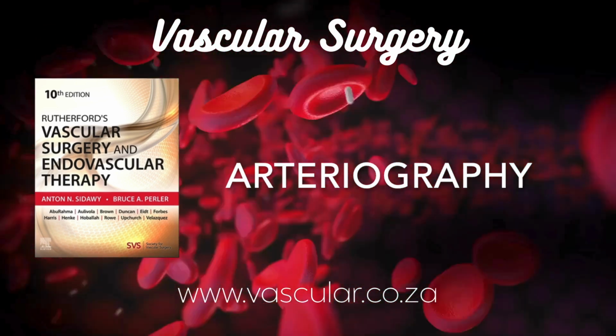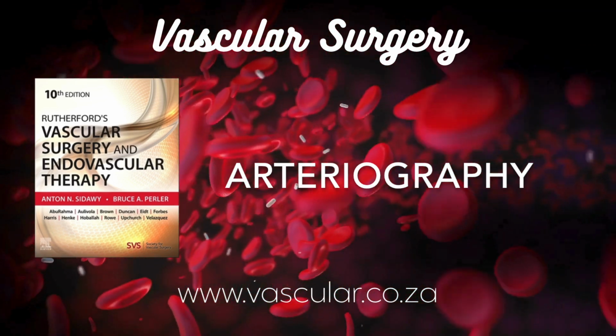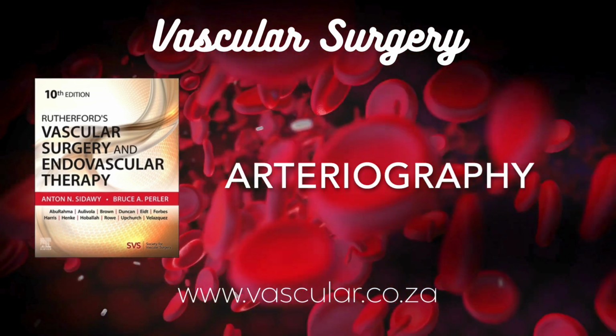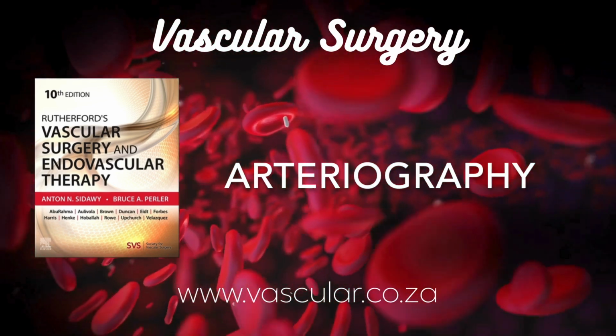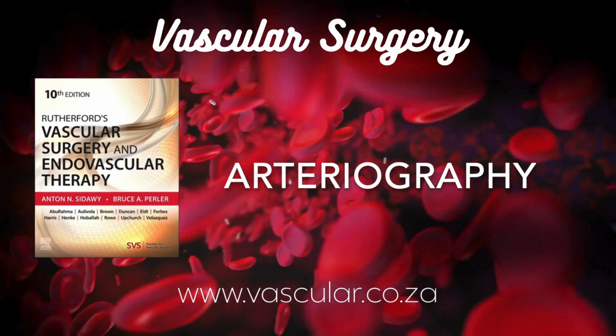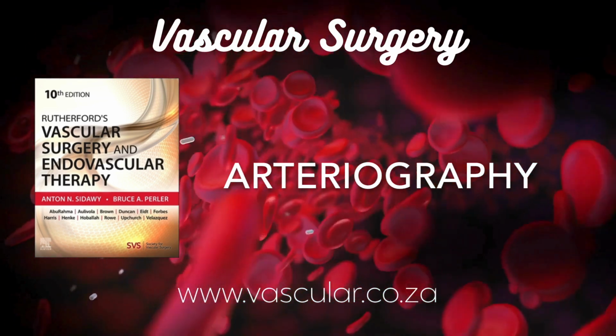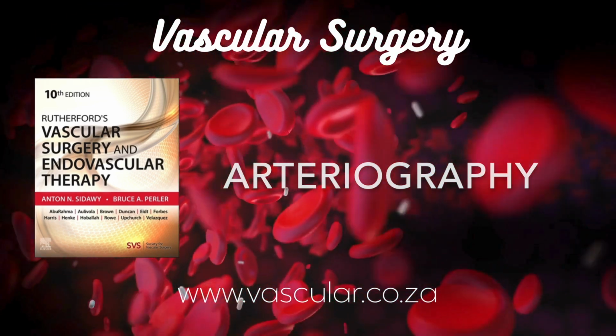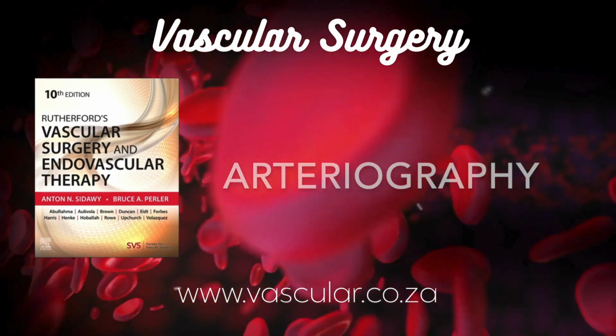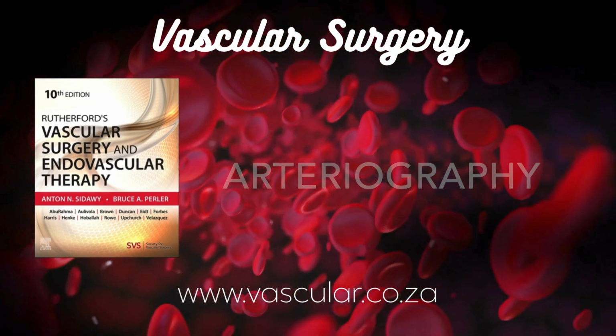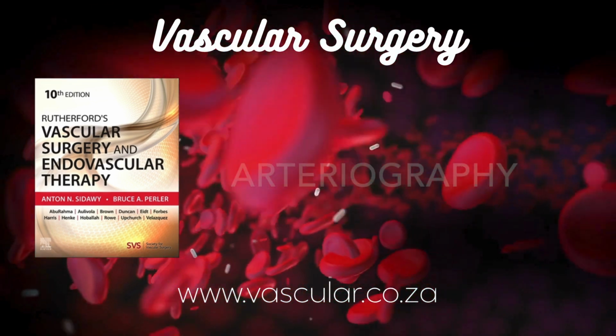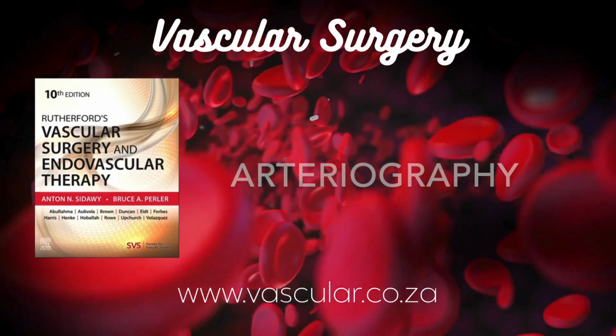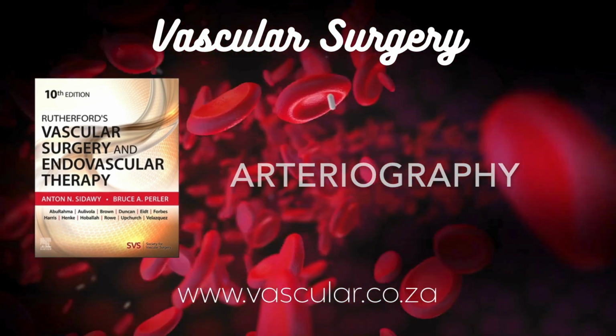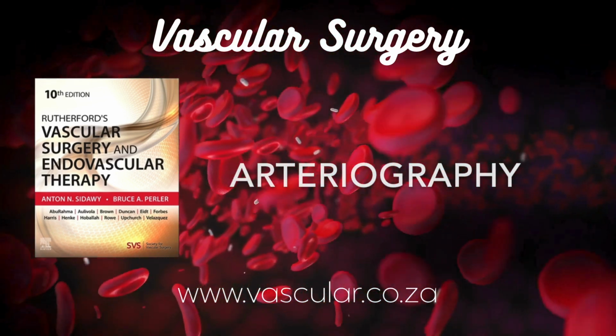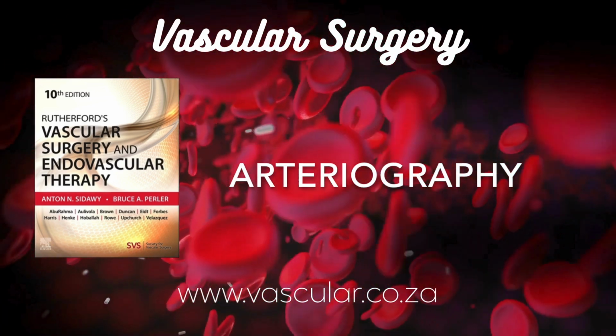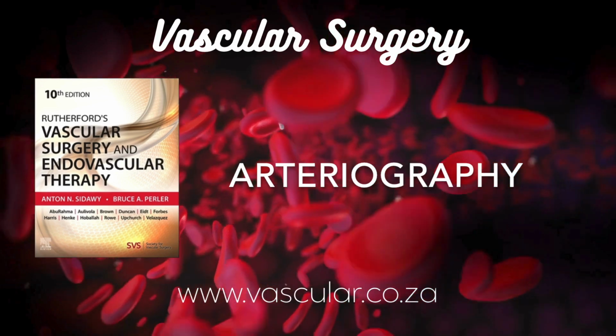What's the catch? The catch is movement. If the patient moves at all between when the mask is taken and when the contrast flows through. Like breathing. Or bowel gas moving. Exactly. Any movement means the background in the later images doesn't perfectly match the mask anymore. So when you subtract, you get artifacts, ghost images, or dark areas that mess up the picture. That's why keeping the patient perfectly still is absolutely critical for good DSA. Okay. And timing matters too. Yes, especially if you're injecting far away from where you're imaging. You usually want to start the injection just before you take the mask, so the contrast arrives in the viewing area right after the mask is set.